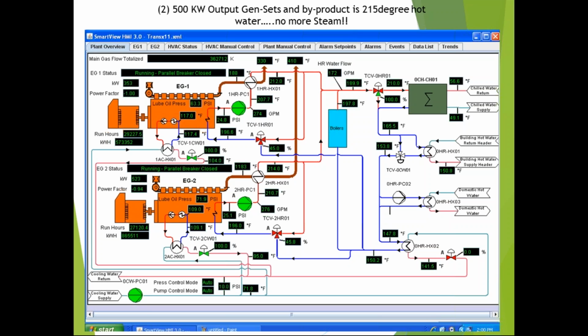Well, this heat recovery unit is a tube bundle, but what goes over that tube bundle is the exhaust air of the engines. The exhaust air coming out of the engines is almost 1,200 degrees coming out of the cylinders, right? So then that heat, that sensible heat, but it's in a vapor. It's air temp, not water temp, right? It's not a totally saturated element. Then it comes out of that heat recovery at 400 degrees.